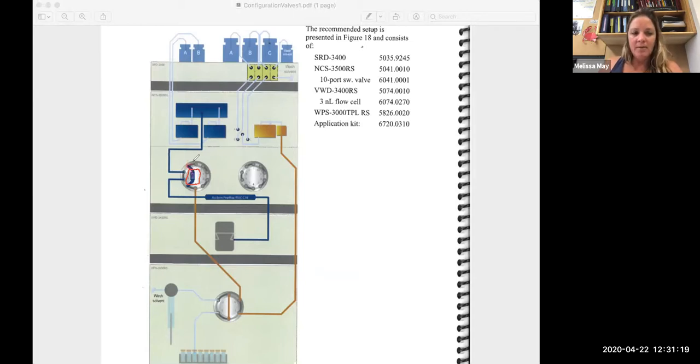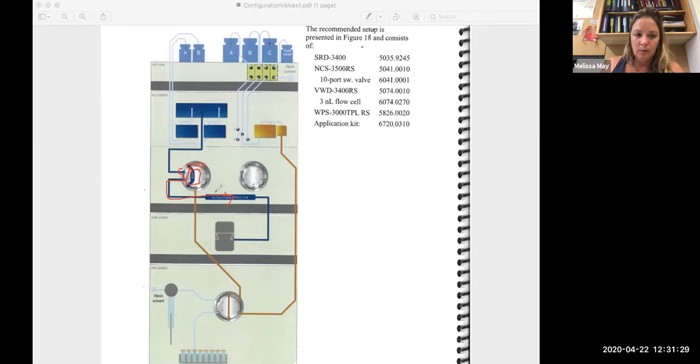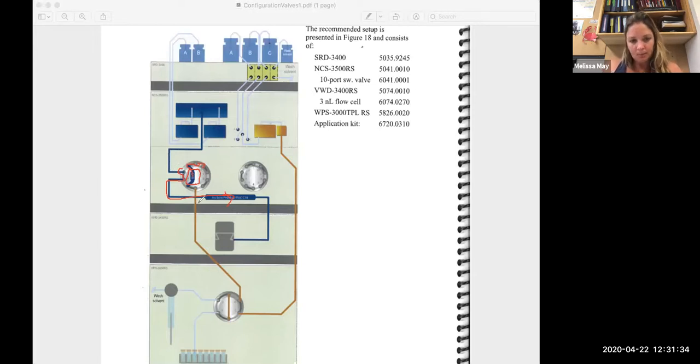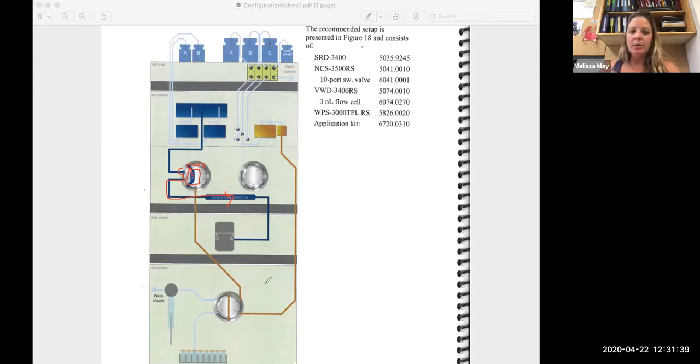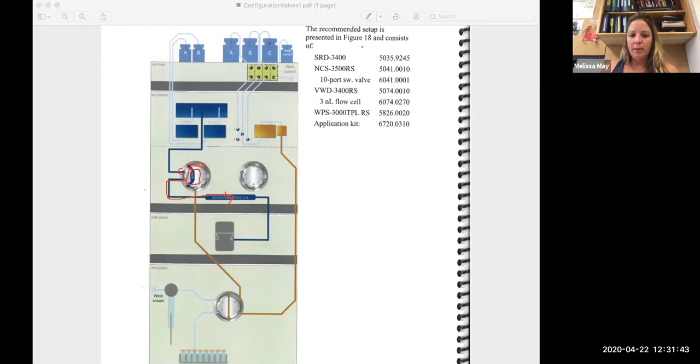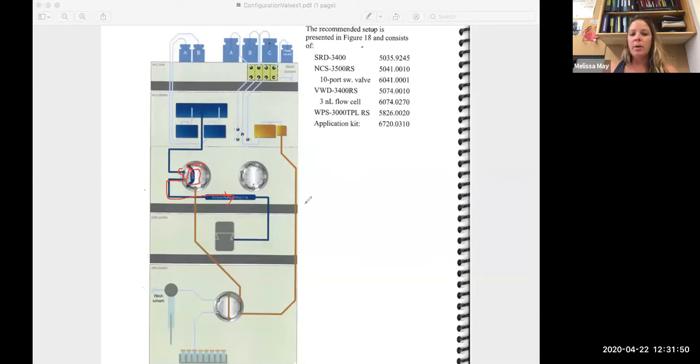It's going to come onto your column, and then this allows you to set up your gradient. And so by varying that valve position, you're now putting your trap column in line so that whatever is coming up from the autosampler, and effectively what's coming from the loading pump, is going onto your column instead of going to waste.